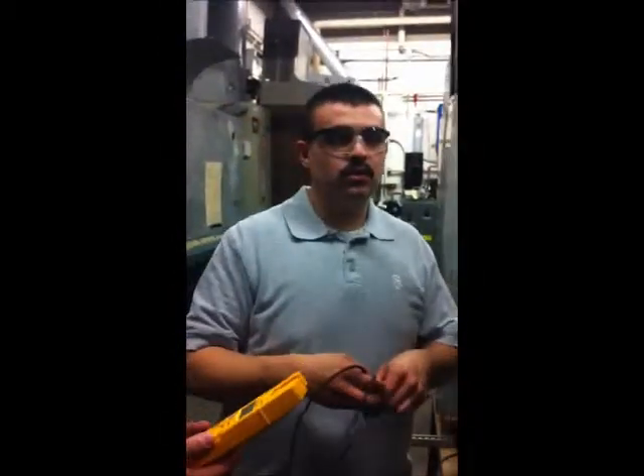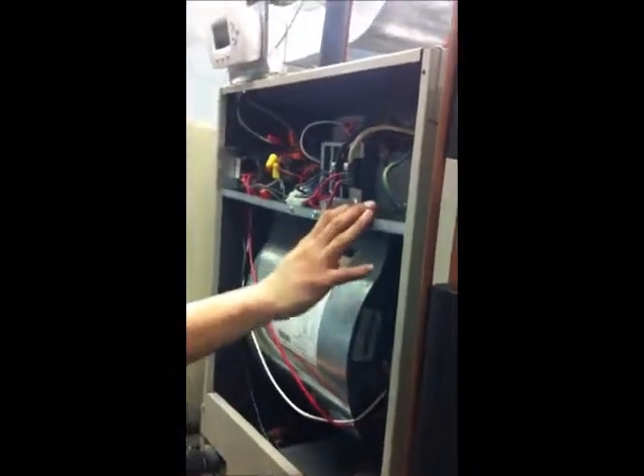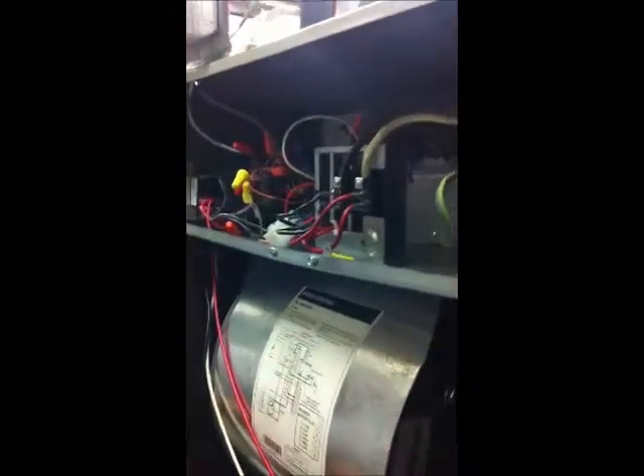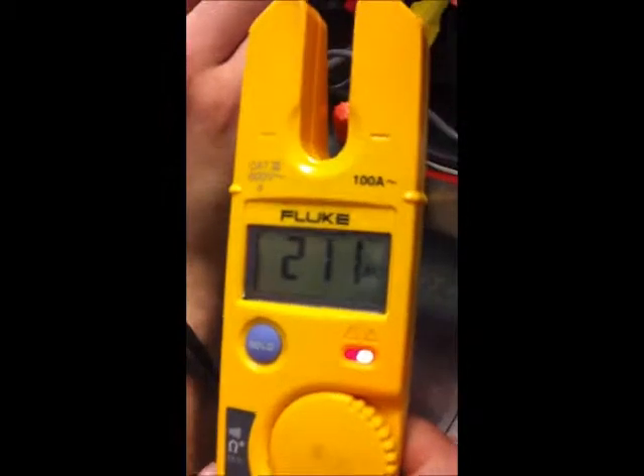Okay, so now that we know that we have 210 volts coming into the furnace, now we're going to check if we're getting voltage to our transformer, which steps down from 208 to 24 volts. So we're going to come in here, go to common and to line, and as we can see we're reading 210, which means we are getting our voltage supply.